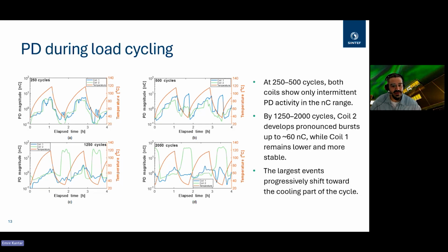As you see, some higher partial discharge magnitudes start happening as the number of cycles increased, and the higher magnitudes start to happen at different stages. In the beginning, it was happening at the peak temperature. When we hit the peak temperature, we had the highest PD, but over the aging, after 1000 or 2000 cycles, we see that higher PD was happening during the cooling. So it tells us some mechanisms are changing over time.